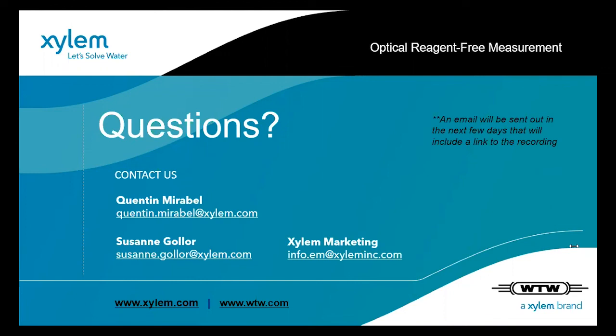In total, you have 200 methods available, with method updates provided. Most have barcodes and are automatically selected, and if you use test kits in rectangular cells, they automatically switch to the correct measuring range. So the photoLab 7000 series provides highly precise, easy to use routine analysis, and the UV-VIS meter gives you the option of optical reagent-free measurement using only UV, since we scan in the UV range. Everything is set up - you just unpack it and use it, very simply.